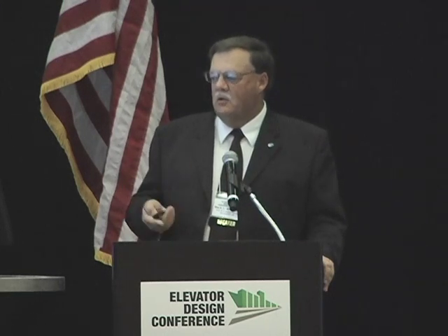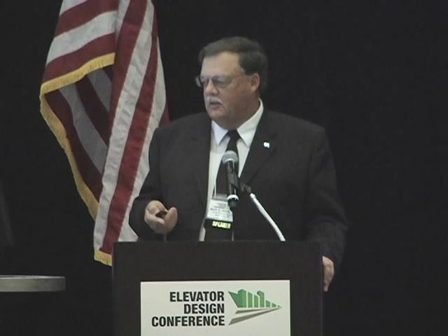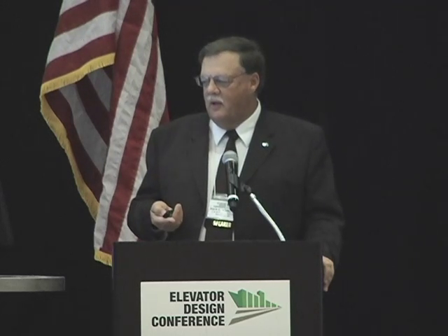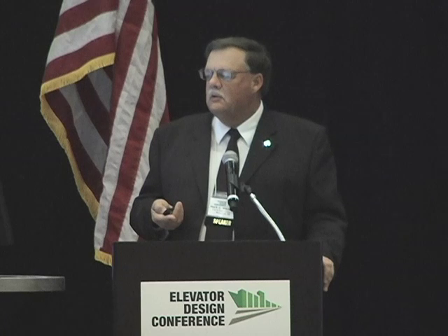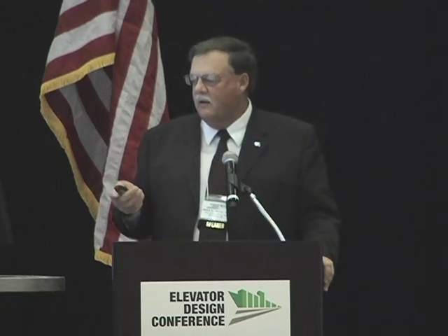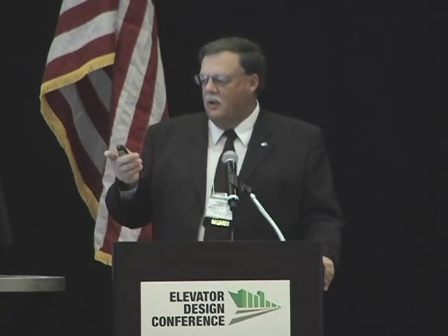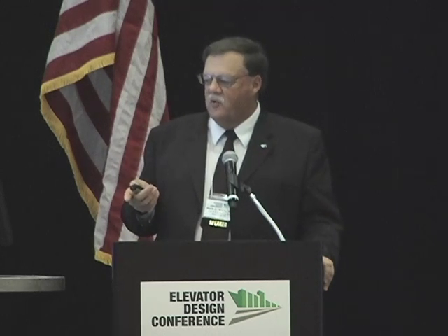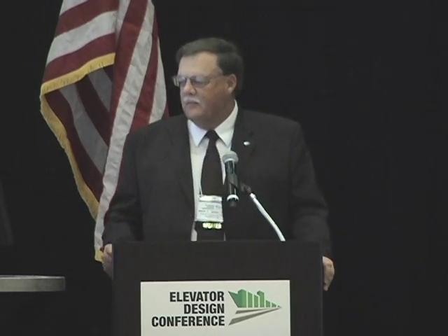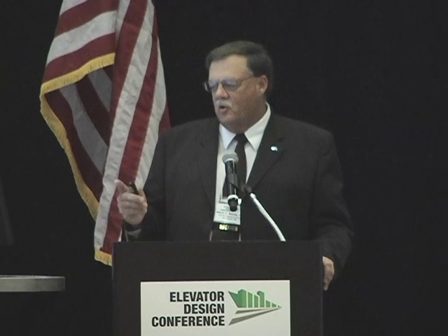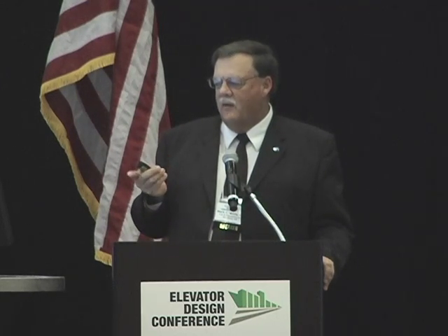We have a utility transformer, revenue meter, main equipment with a main breaker and some feeders, and we're going out to an MCC at a dock, some 480-volt lighting systems for the site or whatever, a transformer for controls, a transformer for miscellaneous power or an office, and other motor control equipment. I always like to try to keep your control system transformer and your office operational transformer off of your main service.